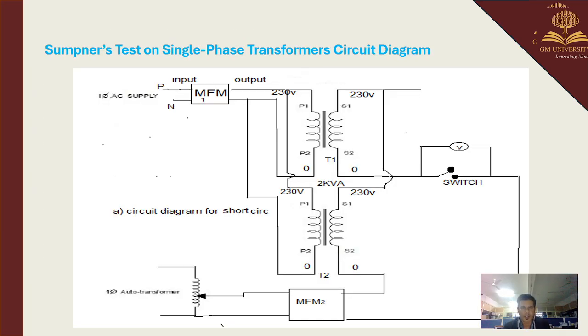So this is the circuit diagram. You can see that the input of multifunction meter 1 should be connected to the AC supply. Then the output of the multifunction meter should be connected to the two transformers, that is T1 and T2. P1 and P1 should be shorted, similarly P2 and P2 should be shorted, and that should be connected to the output of the multifunction meter.